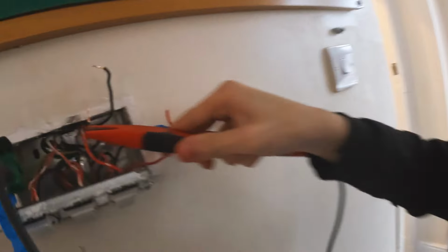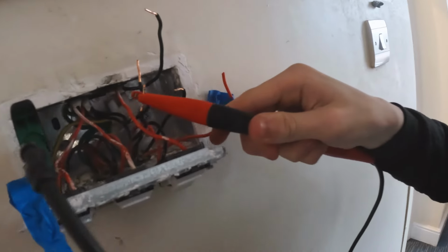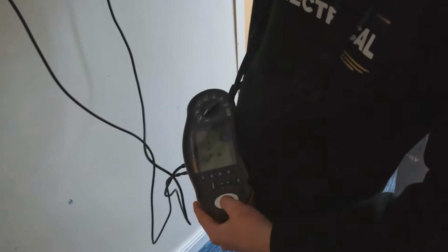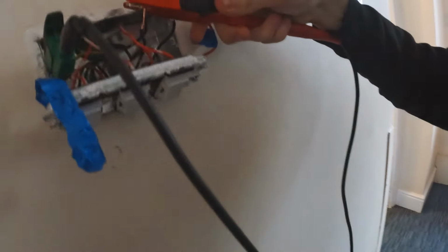Right then, so test the one coming in. So that's the one down. 0.24, right, so it's most likely the feed side, but let's test them just in case they are leaking out. Yeah, greater than 2000. I can't see that decimal place. They're all good. So these lights, we don't need to touch any of these. So literally we're left with those outside lights here and that room there, and there's a couple of storerooms at the back. So win-win, we're getting down there, we're chopping.